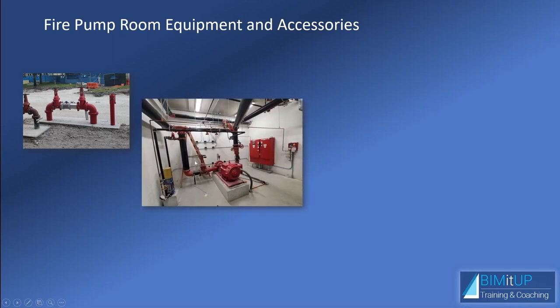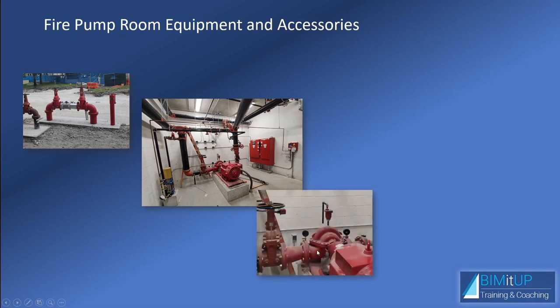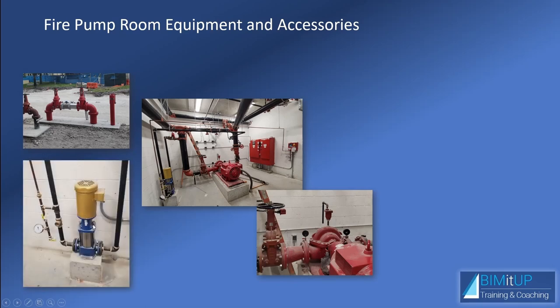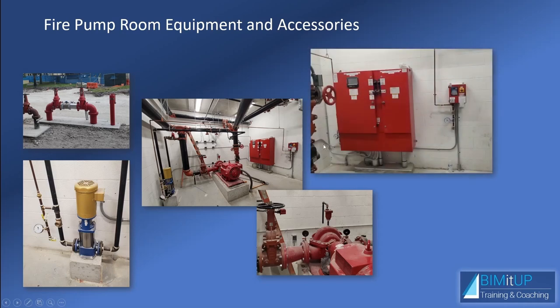So, another fire pump room. You see the layout here. Typically, you obviously need some drains from the casing. It'd be imperative to have a floor drain in a fire pump room. And then you can see that the main pump has sensing pipes going to the pump controller, and the jockey pump also has some sensing lines going to the jockey pump controller. So here you see that casing again with that eccentric reducer. The jockey pump, you have your main controller here with the jockey pump controller.